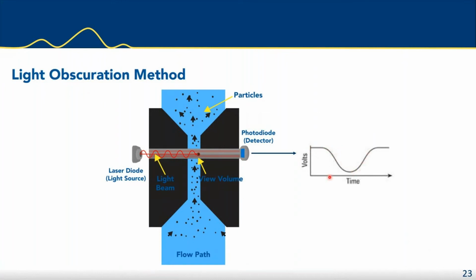So it's this delta here that's measured to give you the magnitude of the particle, because typically when there's no blockage, the reference voltage goes all the way across, and it's a known reference. So to get the size, you'll subtract the delta from the reference, and that'll give you the size of the particle blocking the light. And that's basically how it works. It's a pretty simple concept. It's also known as light blockage, light extinction.